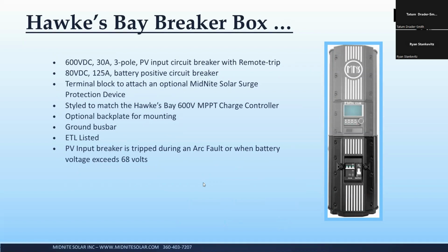So the breaker box, again, not really any rocket science here. It's a cast box that matches the charge controller. The one thing I'm going to point out here that's really nice is the breaker for the PV side. We had a lithium battery manufacturer come to us years ago before we even built this product and said that they had a charge controller, who I won't name, that failed internally. And when it did, it passed high voltage through to their battery, and their battery's BMS, because the voltage was so high, when it tried to open, it arced over and shorted the FET internally, and it fed the lithium battery like 400 and something volts. So we really opened our eyes on that one.